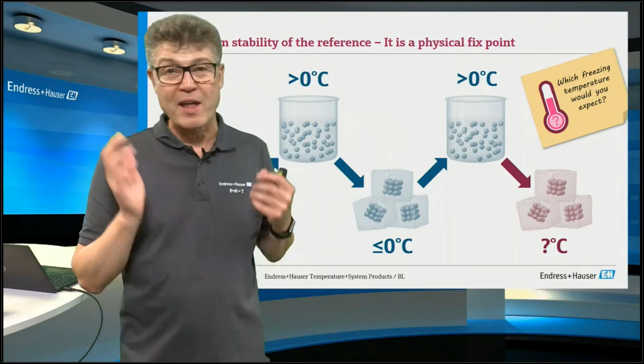And so a fixed point does not need to be calibrated, because this is the definition of a fixed point, that it cannot change. And like the ice can be melted and frozen again and melted and frozen again, this Curie material will make the transition. So there's something in the crystal happening. And so there is no need and no possibility to change it. So it is not necessary and not possible to calibrate it.